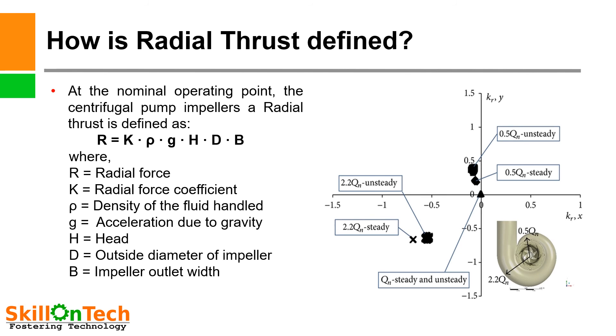So how can we define it? At the nominal operating point, for centrifugal pump impellers, radial thrust is defined as R = K × ρ × G × H × D × B, where R is the radial force, K is the radial force coefficient, ρ is the density of the fluid handled, G is the acceleration due to gravity, H is the head imparted by the pump, D is the outside diameter of the impeller, and B is the impeller outlet width.